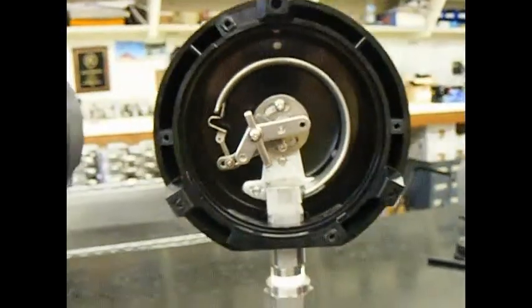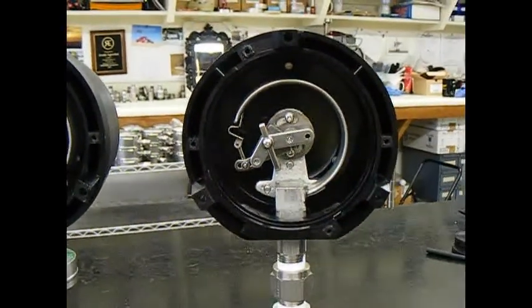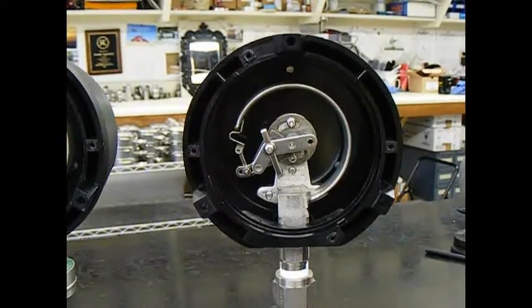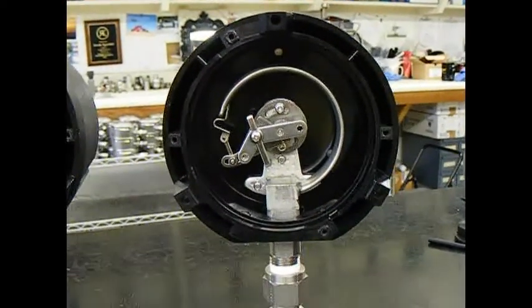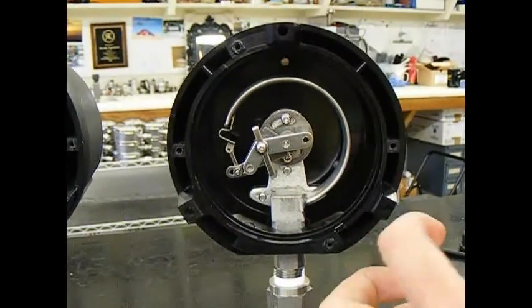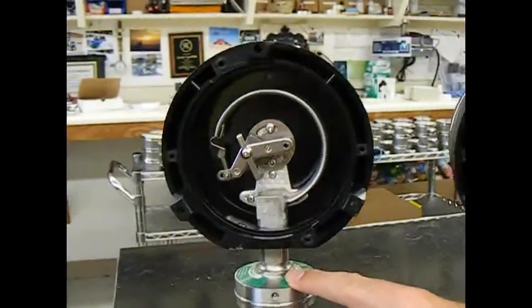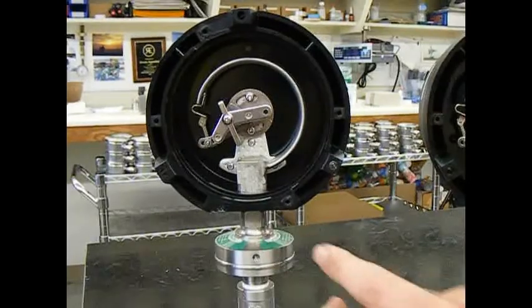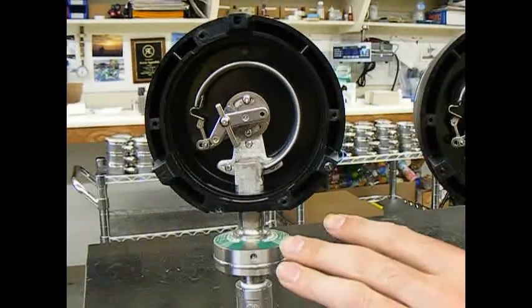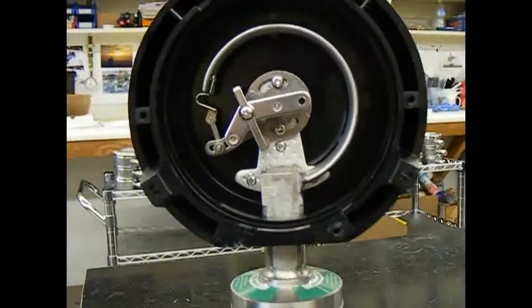As you can see with this unit you're looking at now, the sawtooth gear grinds up against that pinion at just about the exact same rate that the water hammer or pump we're trying to simulate is generating that energy all the way into the metal components of the gauge. Whereas over here on the left, the Pulse Plus unit dampens the pulsation to the point where you won't see that sawtooth gear move hardly at all.